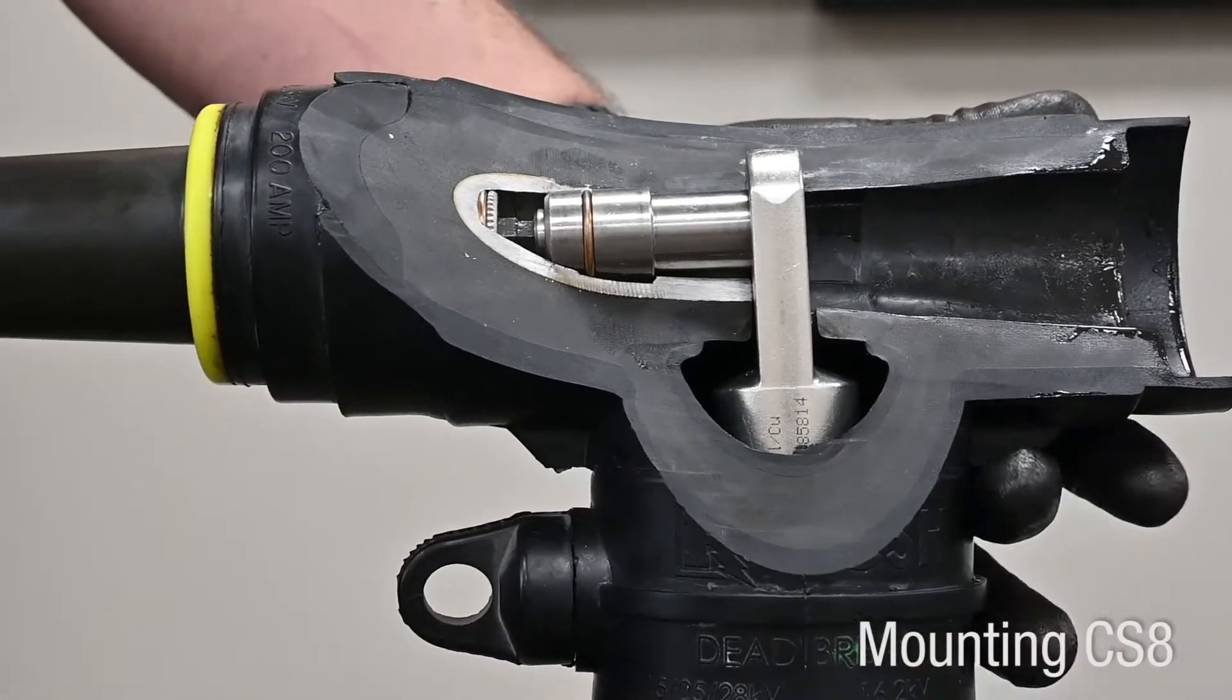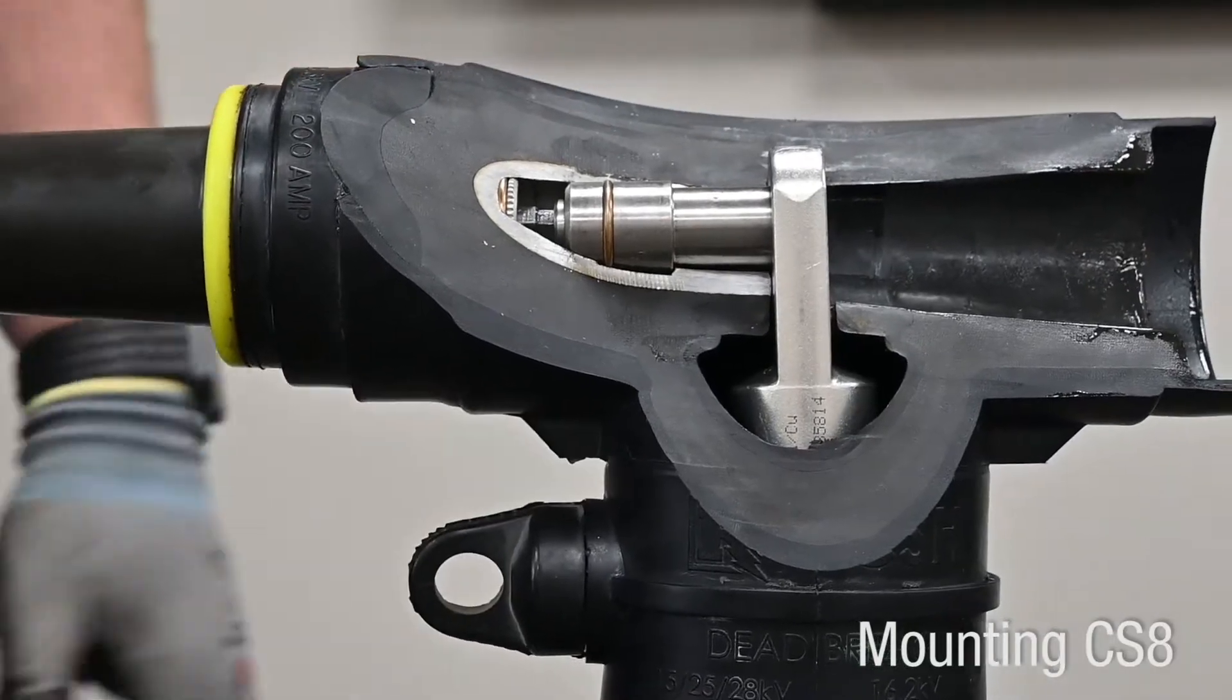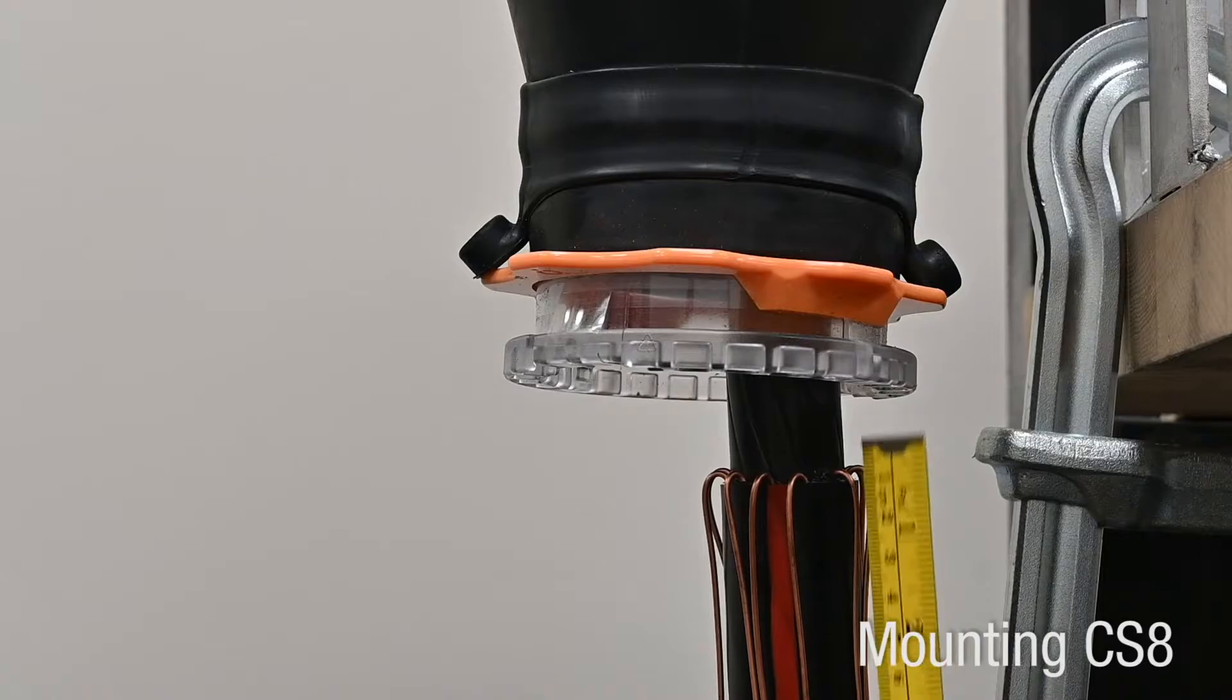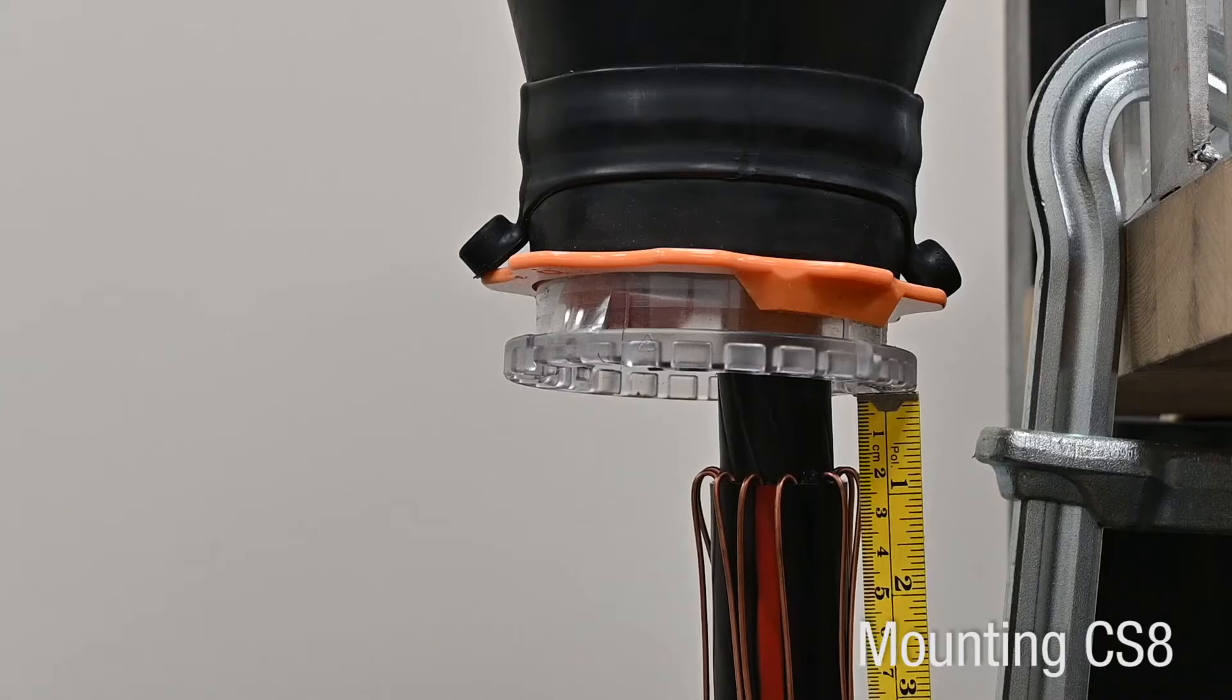Lift up on the CS8 body to confirm that the assembly is locked with the fastener through the lug hole. Measure distance from the edge of the core to the jacket cutback. Note the measured distance. This will confirm correct positioning after mounting.